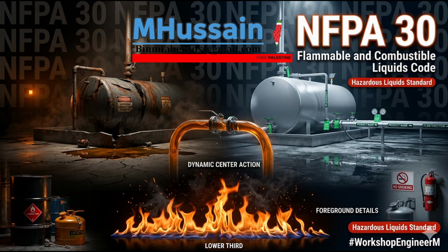It really does. Okay, so we know the chemistry, we know the vapor dynamics. The next step for a facility engineer is containment geometry. How do we legally put these liquids inside a building? Which brings us to MAQs, or maximum allowable quantities. Right, Chapter 9. This is where we shift from physical chemistry to architectural geometry. Table 9.6.1 is essentially the Rosetta Stone for facility planners. And if you look at the baseline numbers in that table, they are shockingly low if you don't have active fire protection. Like for Class IA, the most volatile, if you want to store it in a standard unsprinklered building, your legal limit is 30 gallons. 30 gallons. To put that in perspective, a standard industrial steel drum is 55 gallons. So you can't even have one full drum. Nope. The code is basically telling you that one full drum of Class IA in an unprotected space fundamentally violates the safety envelope of the entire building.